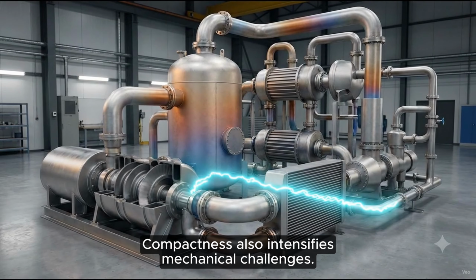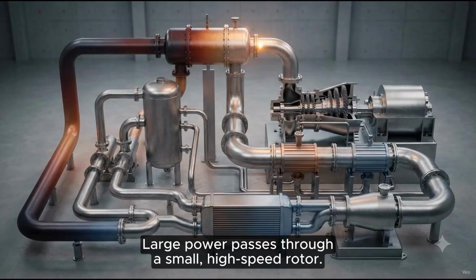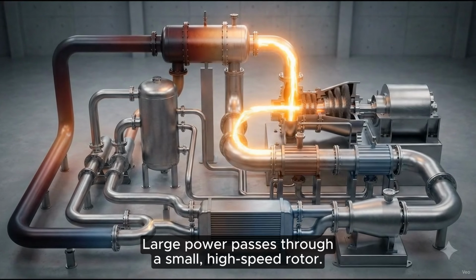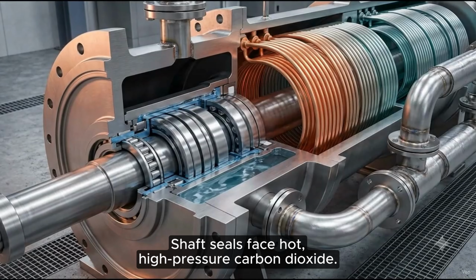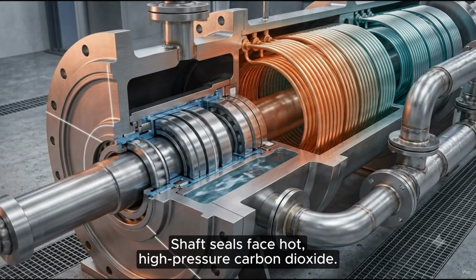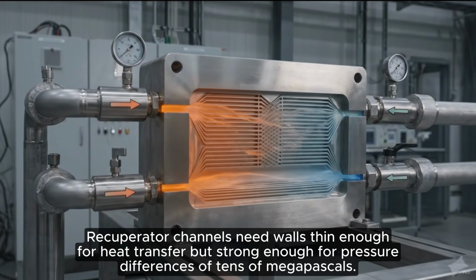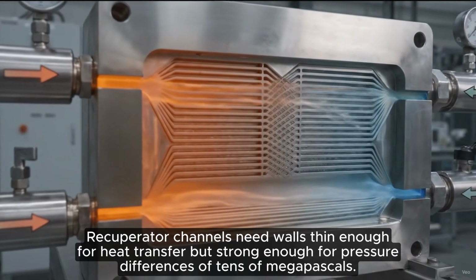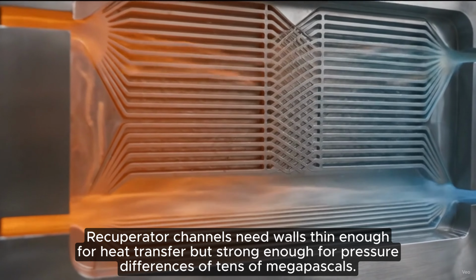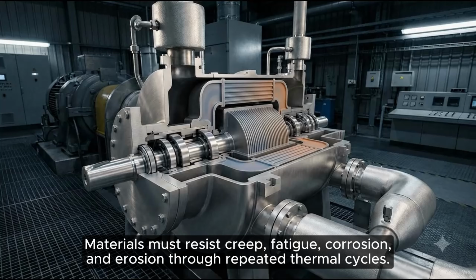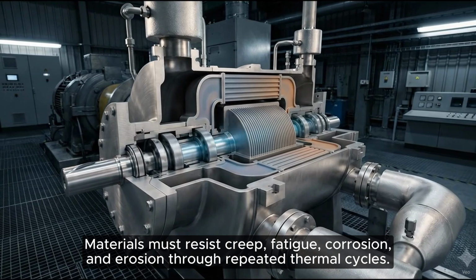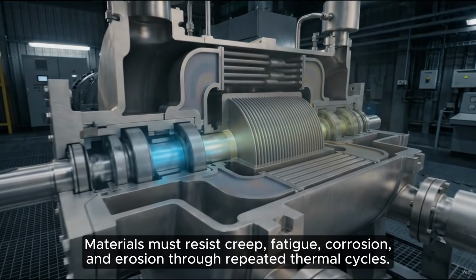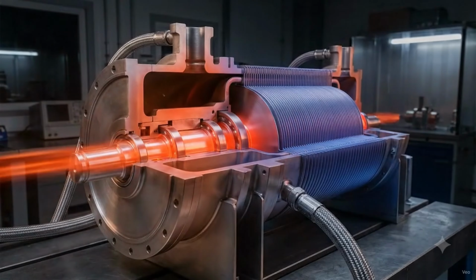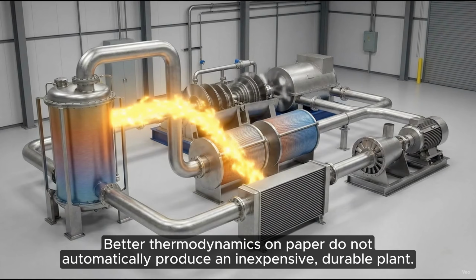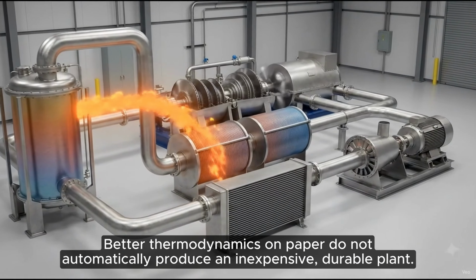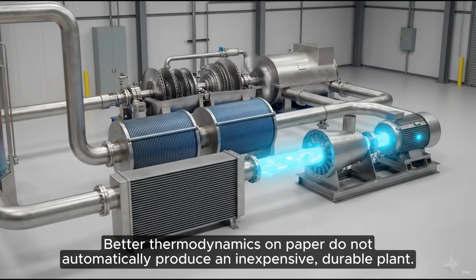Compactness also intensifies mechanical challenges. Large power passes through a small, high-speed rotor. Shaft seals face hot, high-pressure carbon dioxide. Recuperator channels need walls thin enough for heat transfer but strong enough for pressure differences of tens of megapascals. Materials must resist creep, fatigue, corrosion, and erosion through repeated thermal cycles. Better thermodynamics on paper do not automatically produce an inexpensive, durable plant.